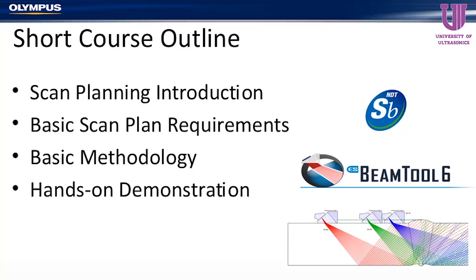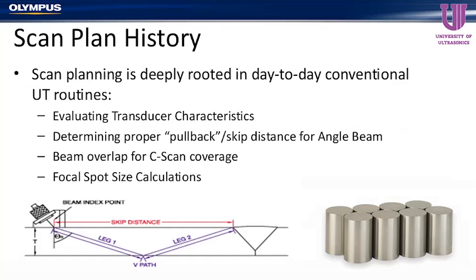We'll start off by talking a little bit about where scan planning comes from and how we look at it and how we use it. Typically, when you talk about scan planning, it's always referred to or tied to specifically phased array — it's a big buzzword. But really, scan planning comes from what we do on a day-to-day basis in any ultrasonic examination, anything dealing with how you implement a UT test, down to transducer selection, down to evaluating sensitivity or resolution characteristics.